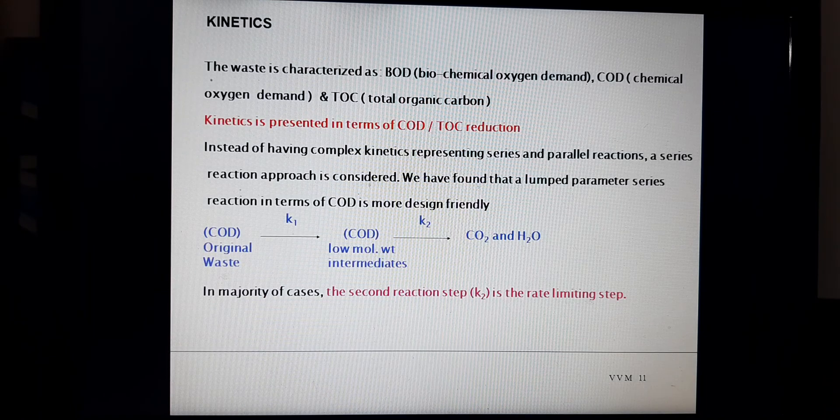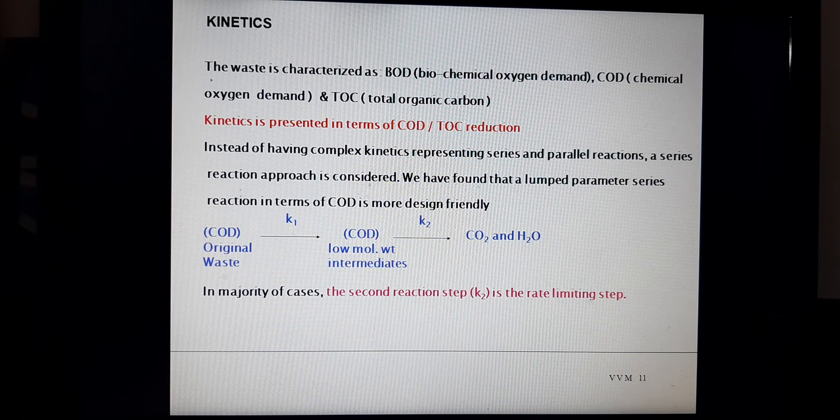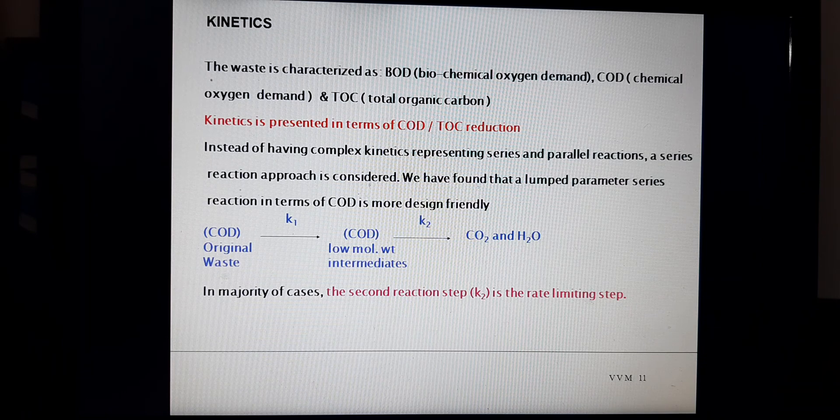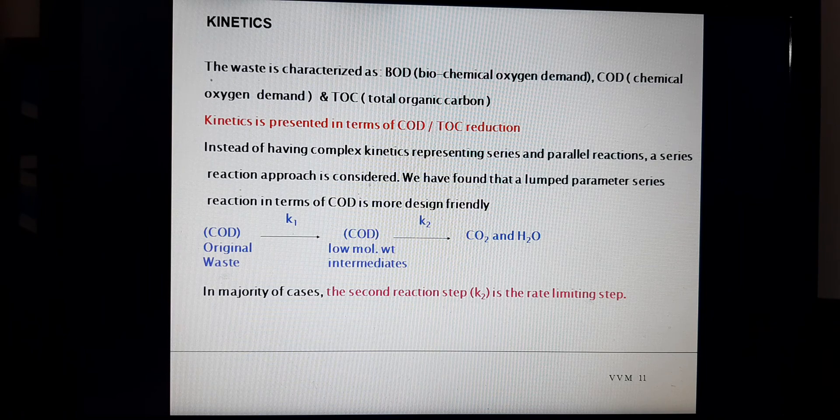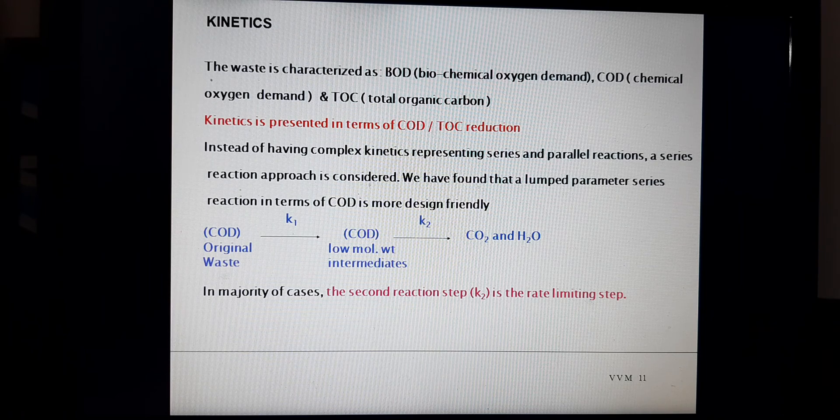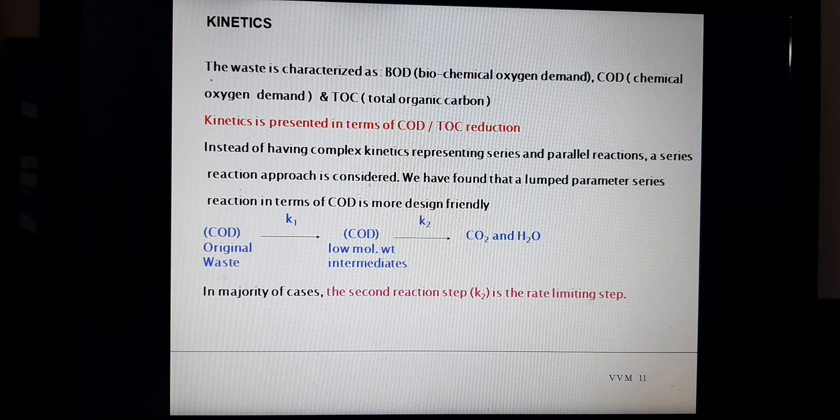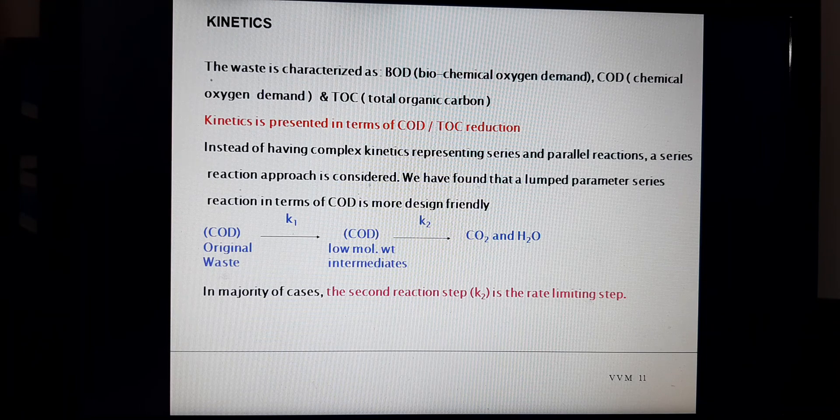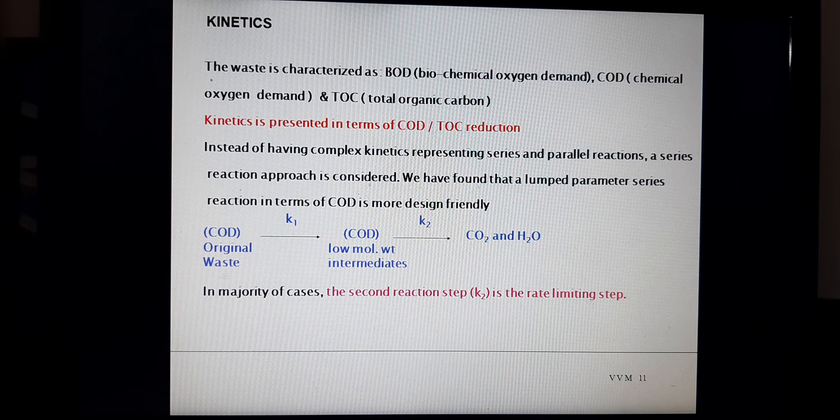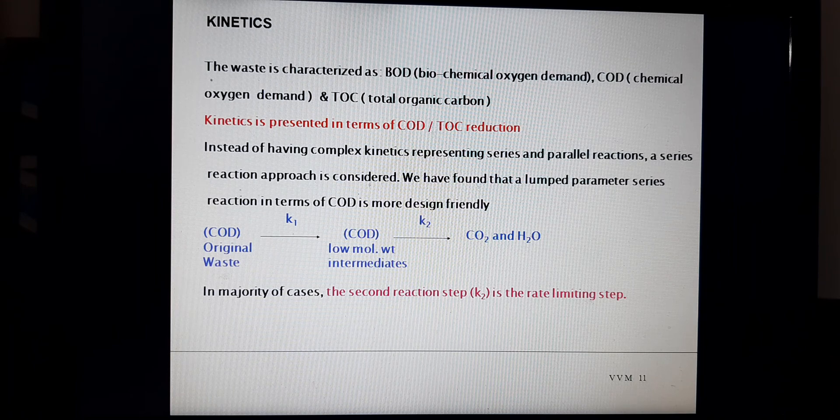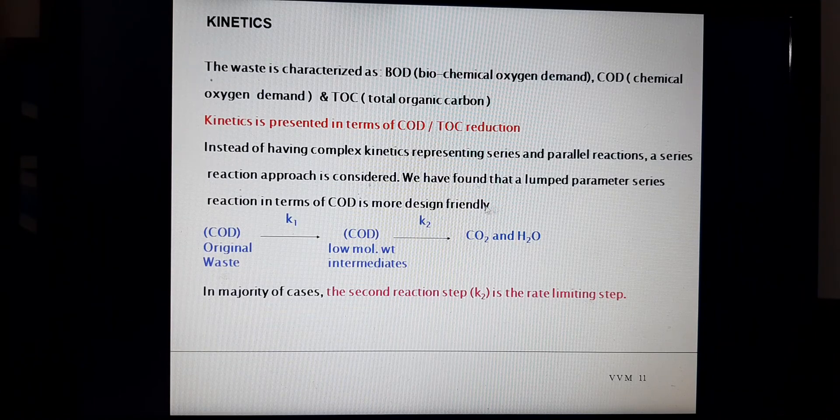For the kinetics of wet air oxidation, waste is characterized as BOD (biochemical oxygen demand), COD (chemical oxygen demand), and TOC (total organic carbon). The kinetics is presented in terms of COD and TOC. Instead of having complex kinetics representing series and parallel reactions, a series reaction approach is considered. We have found that lump parameter series reaction in terms of COD is more design friendly.